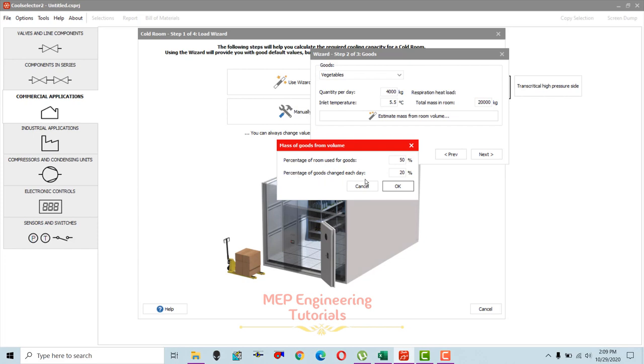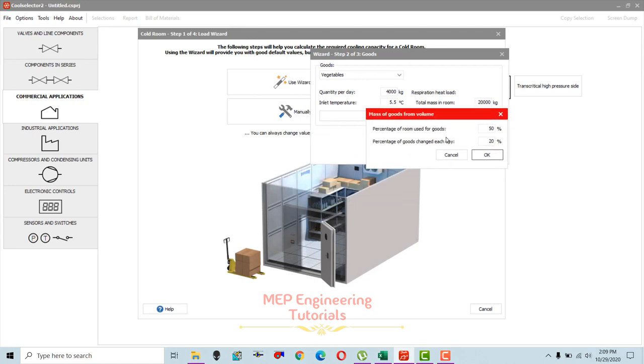You need to provide two things: percentage of the room used for goods, and percentage of goods changed each day. For the room usage percentage, we don't want to fill 80 or 90 percent — we need to keep space so a person can move between racks, easily place or remove goods, and ensure air can circulate between the goods. So we keep it at 60 percent: 60 percent of room volume occupied by goods, 40 percent empty.